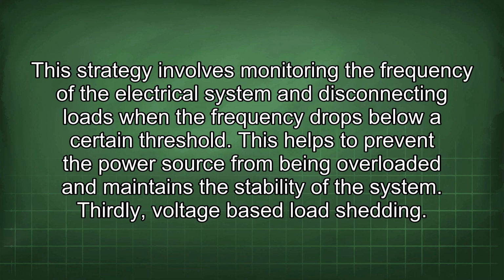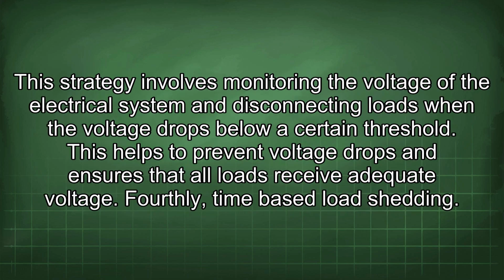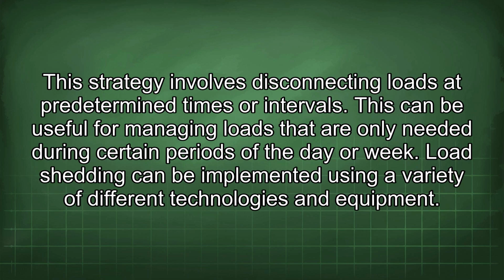Thirdly, voltage-based load shedding. This strategy involves monitoring the voltage of the electrical system and disconnecting loads when the voltage drops below a certain threshold. This helps to prevent voltage drops and ensures that all loads receive adequate voltage. Fourthly, time-based load shedding. This strategy involves disconnecting loads at predetermined times or intervals. This can be useful for managing loads that are only needed during certain periods of the day or week.